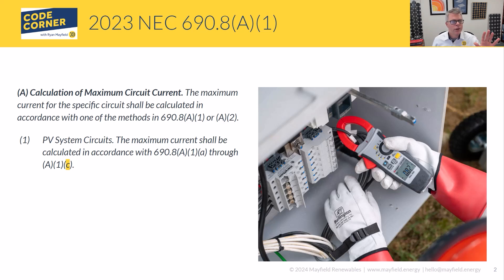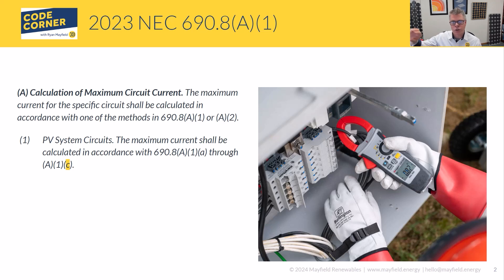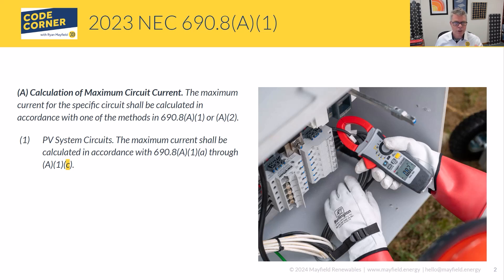The maximum current for PV system circuits is defined in 690.8A1. This covers our circuits straight from our PV modules to whatever our inverter is, our DC-to-DC converter, or something like that — that is what we're talking about with our PV system circuits in this specific case. And the code language takes you through A1A, A1B, and A1C, so let's break those down step by step.